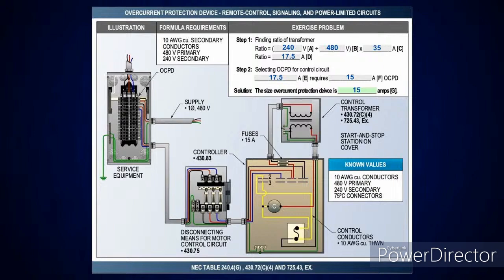And then I'm going to be looking here in the controller. You see I'm checking my fuse sizes here, and for 17.5, I'm going to drop down to the next standard size, which is a 15 amp overcurrent protection device. Right. Okay. So hopefully everybody has followed along with this and seen all the different ways to go about dealing with these control conductors and determining the size for the overcurrent protection device.